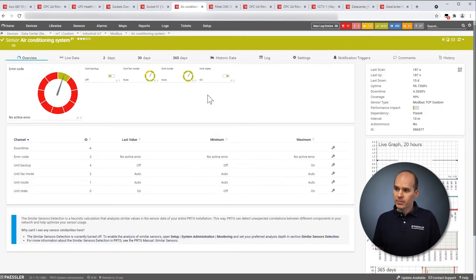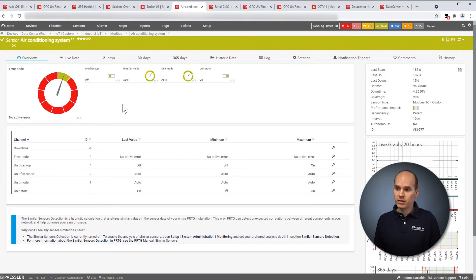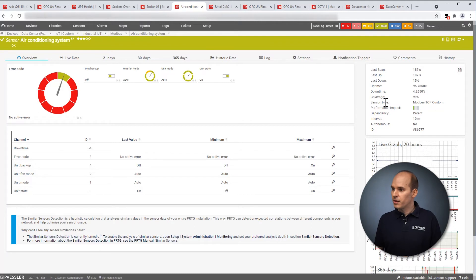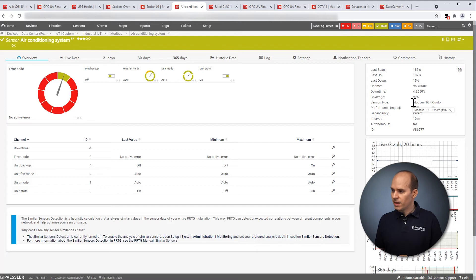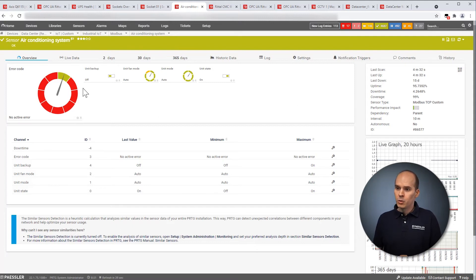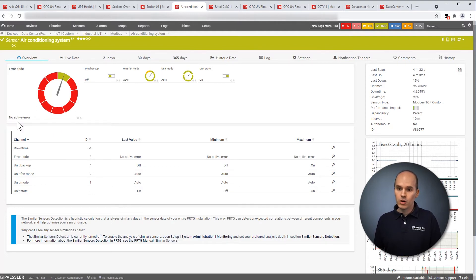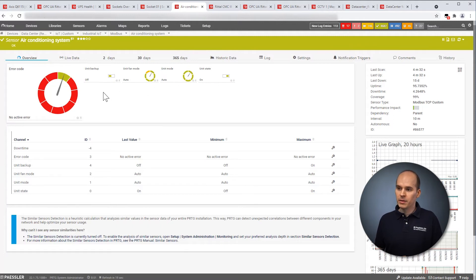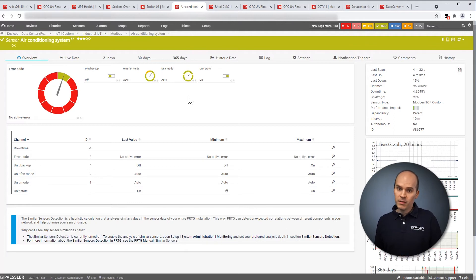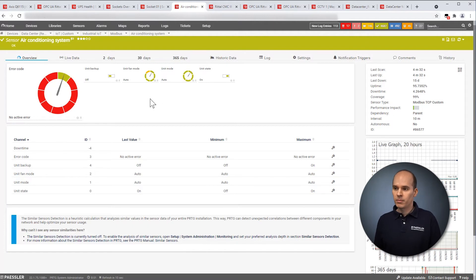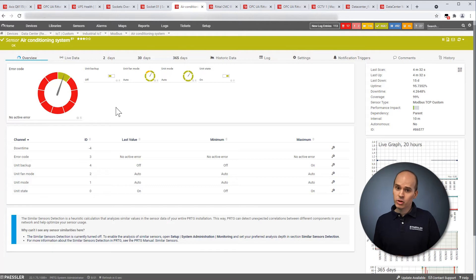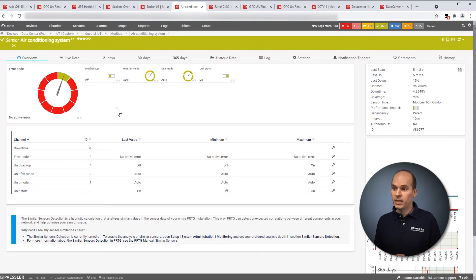We can move on to the air conditioning system, the cooling system in your data center. For this, when we look here on the right-hand side, the sensor type, we have a generic sensor, the Modbus TCP custom sensor. And we have here the error code what we read out of the air conditioning system. We see that here is no active error. And you can see other information in the so-called channels in PRTG. With this generic sensor, you have the possibility to read out certain registers from the Modbus TCP. So for example, another important information could be the inlet temperature or the outlet temperature of your air conditioning system or the fan speed, fan status.